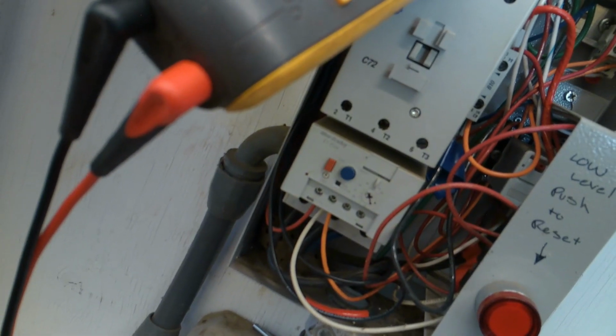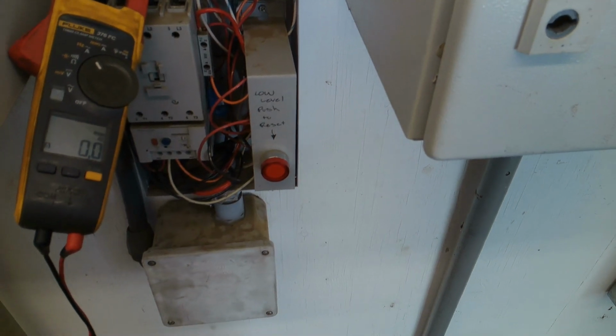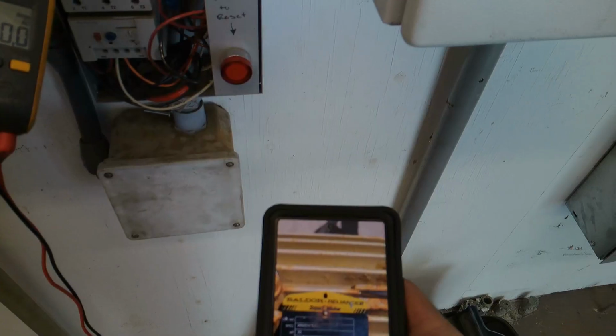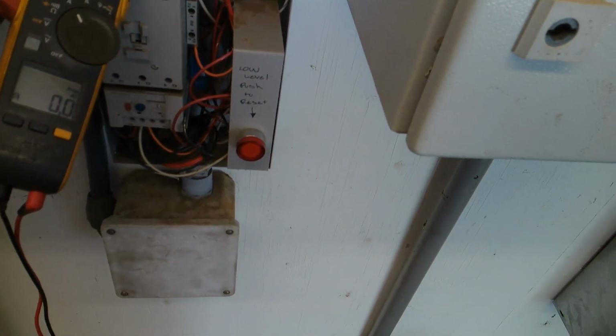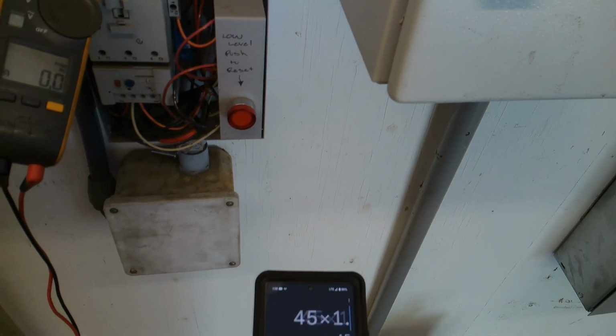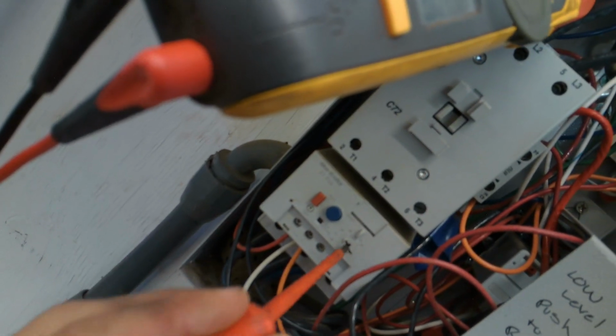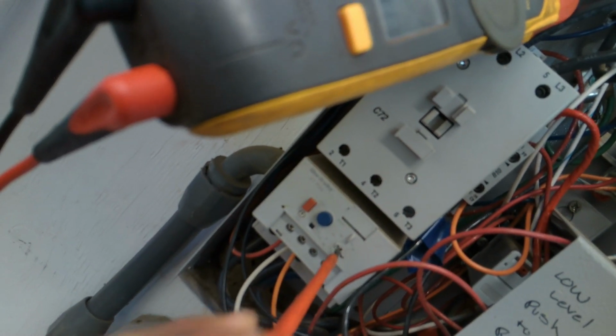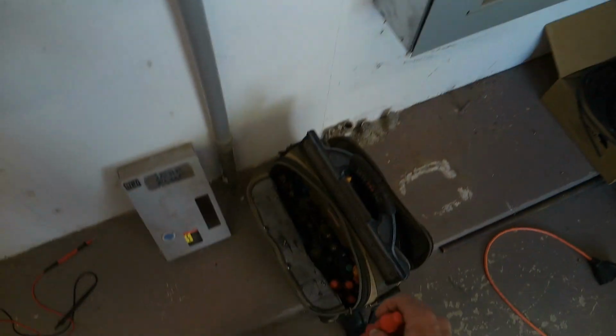Way too high. Boy, the overload is set way too high on this thing. Our motor overload should be set to 1.15 times 45. 45 times 1.15 is 51.75. There. That's where our overload should be. That's not good. Alright, let's try running again.